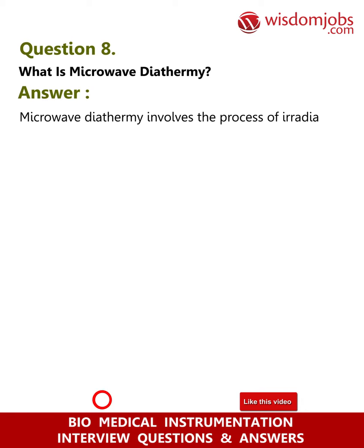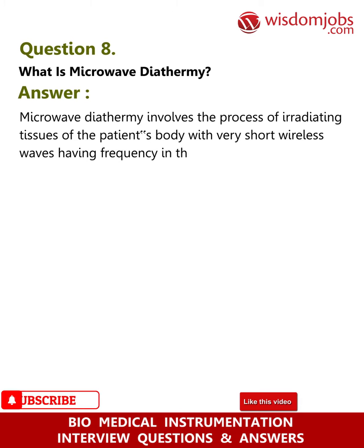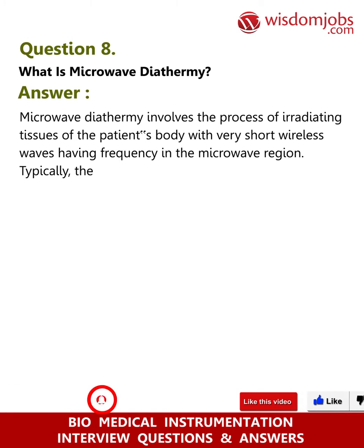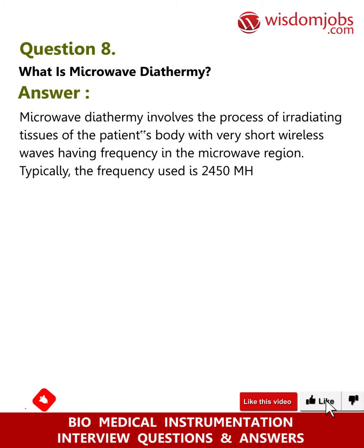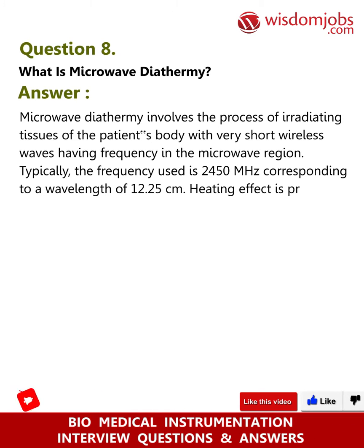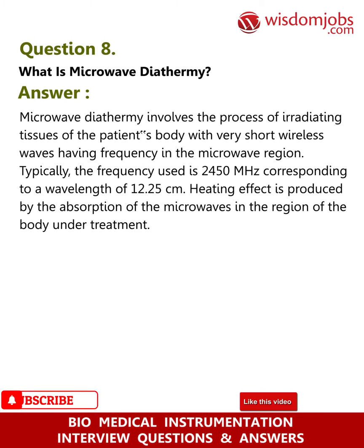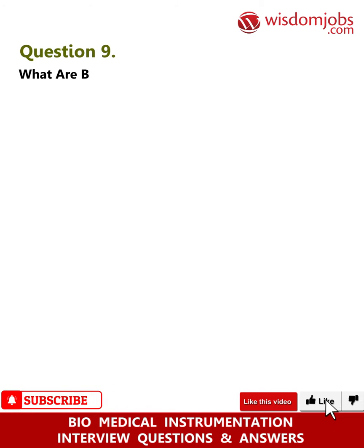Question 8: What is microwave diathermy? Answer: Microwave diathermy involves the process of irradiating tissues of the patient's body with very short wireless waves having frequency in the microwave region. Typically, the frequency used is 2450 MHz, corresponding to a wavelength of 12.25 centimeters. Heating effect is produced by the absorption of microwaves in the region of the body under treatment.